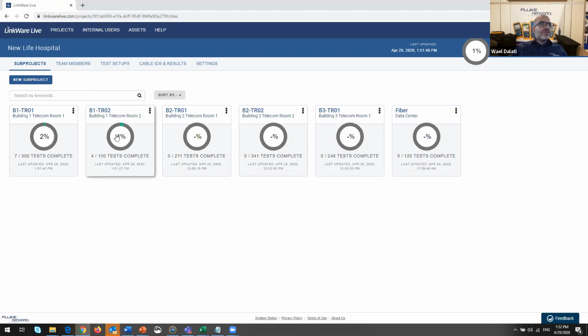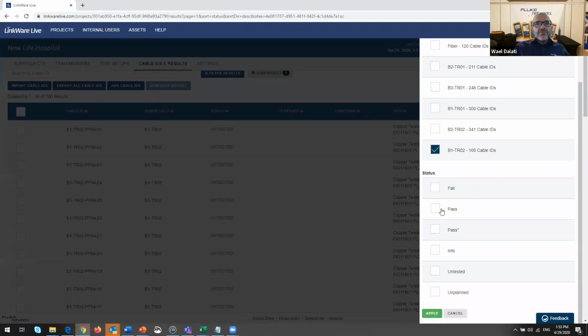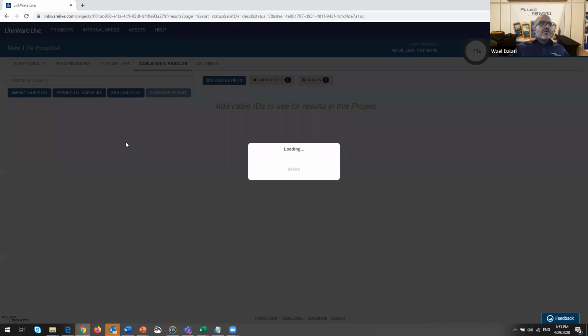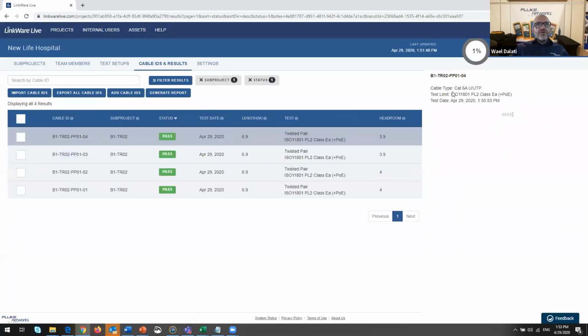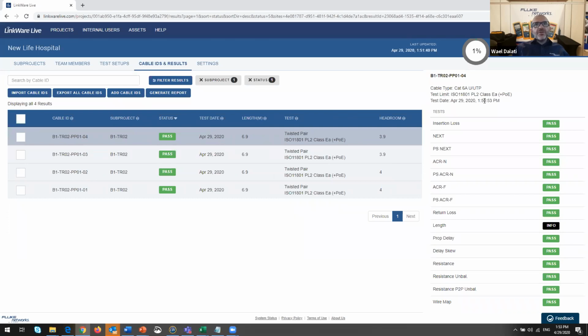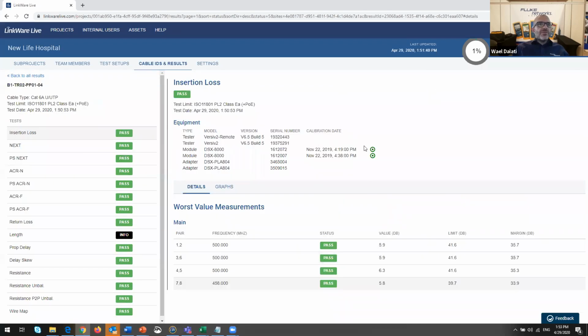If I click on that particular project to see what he has done, then filter by pass, show me the passing links, and apply, I will be able to see which links he passed. When he did the tests, on April 29 at 150, we see all the parameters. And if I need to look one by one, I can see those details. A good thing is that you can see here his tester was within the calibration limit. There is a green flag showing that during the test the tester was in calibration. That's another way to spot if your tester is within calibration and working in good condition. That's also something I wanted to share with you.